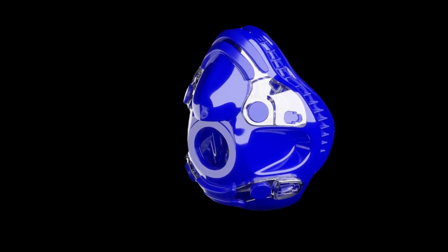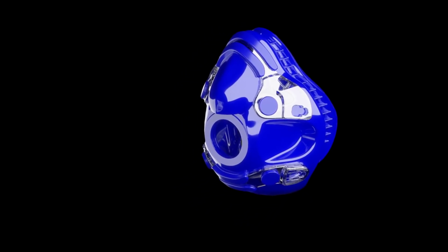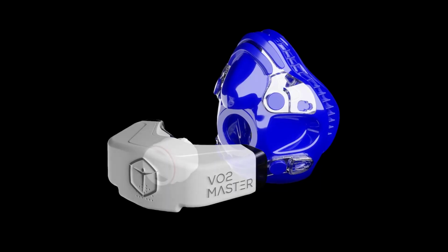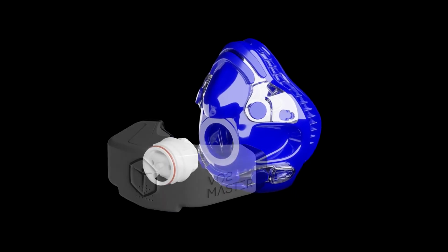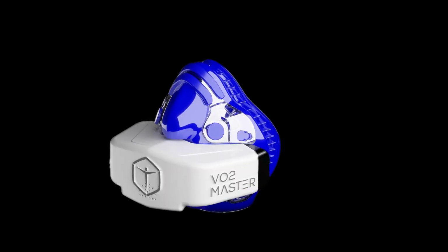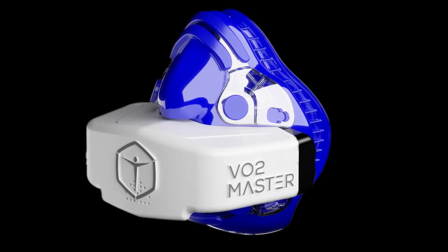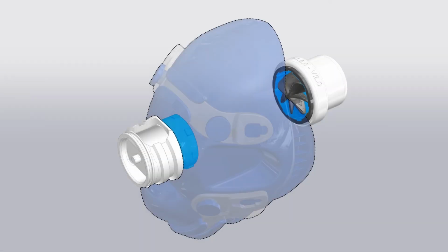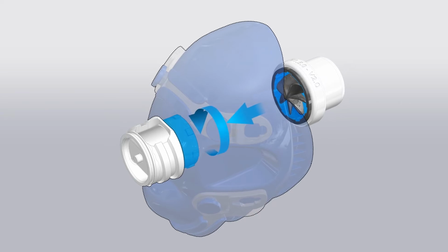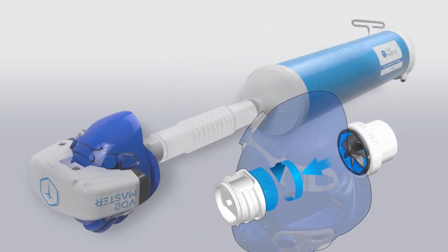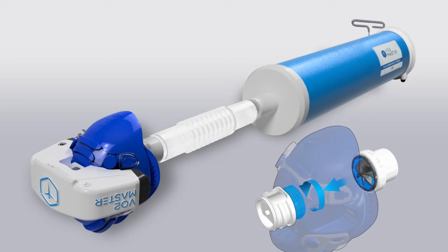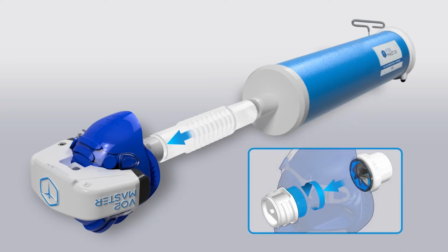For our example, we will be using the blue mask for the calibration process. With the analyzer fully assembled, we will push the user piece through the opening of the blue mask until the mask is resting on the user piece's shoulder. Next, we will thread on the calibration syringe adapter. Once in position, we can now connect the calibration syringe flexible tubing to the syringe adapter and to the syringe.